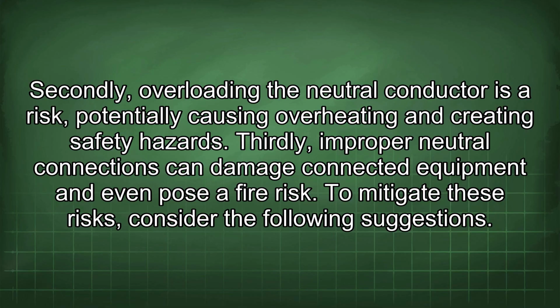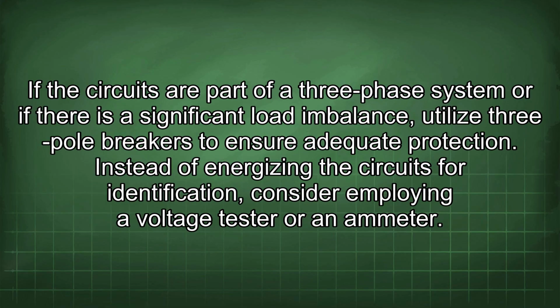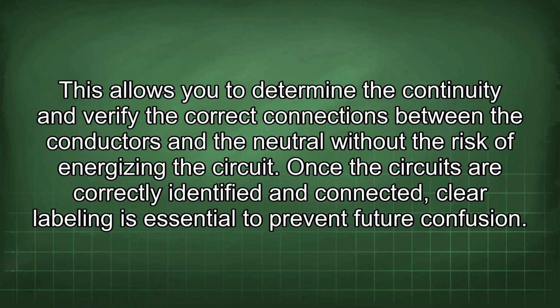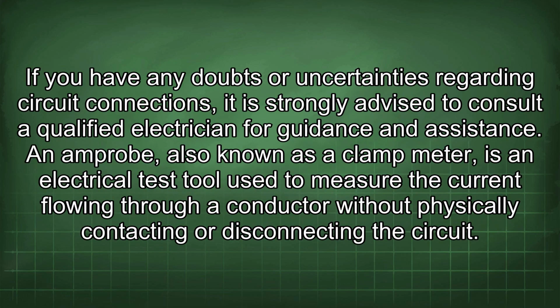To mitigate these risks, consider the following suggestions. If the circuits are part of a three-phase system or if there is a significant load imbalance, utilize three-pole breakers to ensure adequate protection. Instead of energizing the circuits for identification, consider employing a voltage tester or an ammeter. This allows you to determine the continuity and verify the correct connections between the conductors and the neutral without the risk of energizing the circuit. Once the circuits are correctly identified and connected, clear labeling is essential to prevent future confusion. If you have any doubts or uncertainties regarding circuit connections, it is strongly advised to consult a qualified electrician for guidance and assistance.